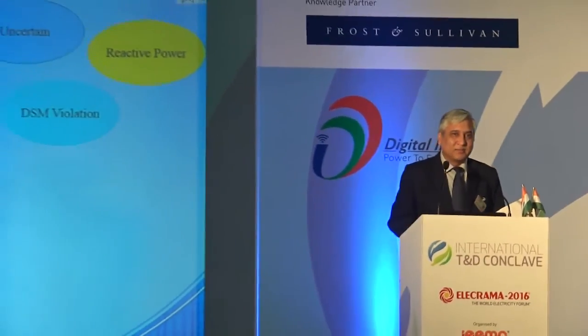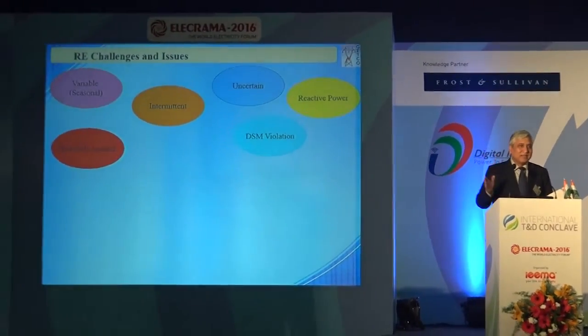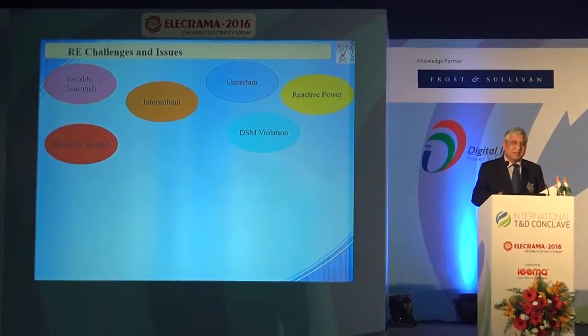Then there's DSM violation, which I won't discuss in detail here. It's a violation that Gujarat state commits with respect to the load scheduling done for central power. We regularly get notices from the central grid operator that we are violating norms, because when wind peaks, it can suddenly jump from 500 to 2,000 megawatt. In that situation we end up in an underdrawing position, meaning there's excess in the grid from both my conventional generation and the wind. So in both cases I'll be above schedule, resulting in underdrawing. This underdrawing issue is widespread in the Indian grid operation, so that's another big issue.